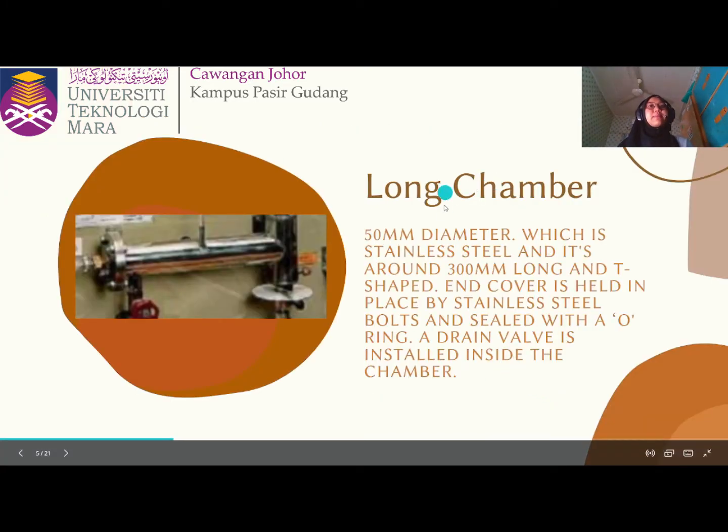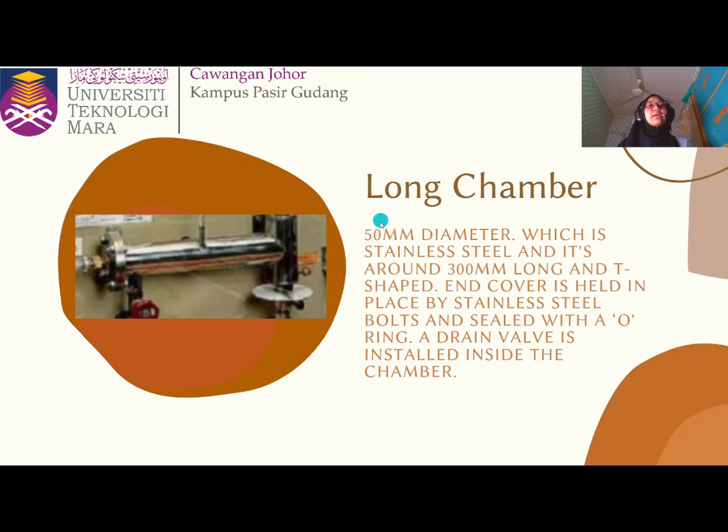The long chamber. It will be a 50 millimeter diameter, which is stainless steel, and it is around 300 millimeters long and T-shaped. The end cover is held in place by stainless steel bolts and sealed with an O-ring. A drain valve is installed inside the chamber.